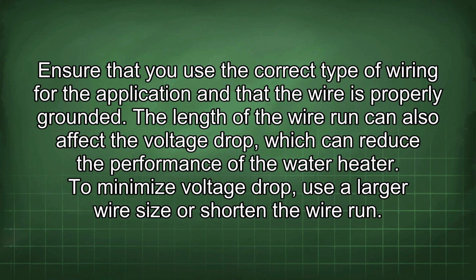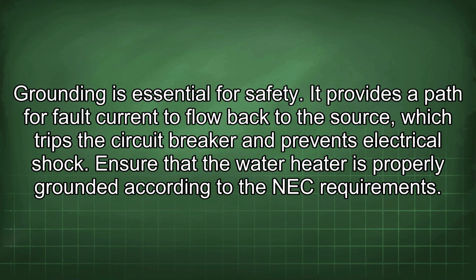To minimize voltage drop, use a larger wire size or shorten the wire run. Grounding is essential for safety. It provides a path for fault current to flow back to the source, which trips the circuit breaker and prevents electrical shock. Ensure that the water heater is properly grounded according to the NEC requirements.